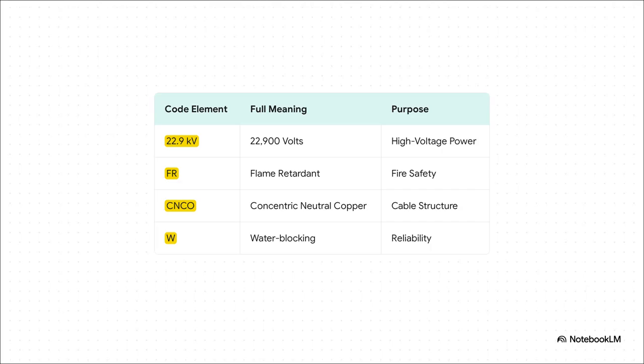So, let's do a quick checkpoint. We've got 22.9 kilovolts for high-voltage power, FR for fire safety, CNCO telling us about the cable's internal structure, and W for water-blocking reliability. You see? Each part of the code tells a vital piece of the story.